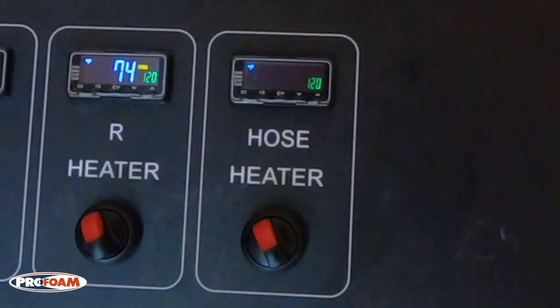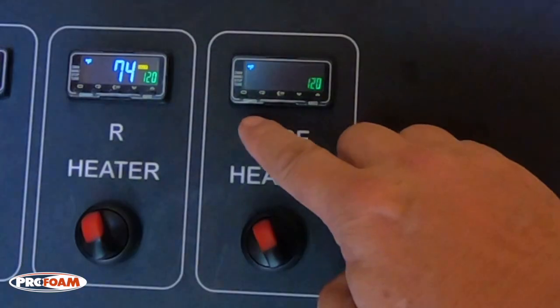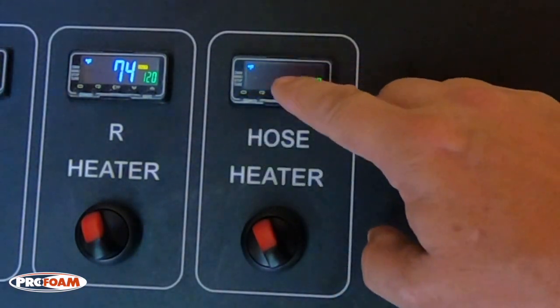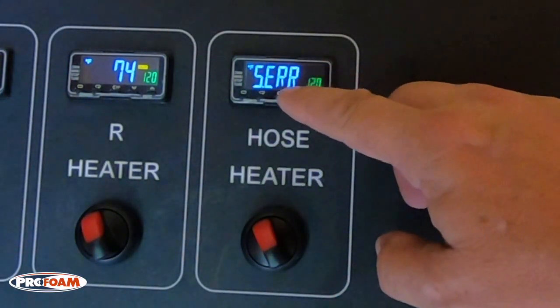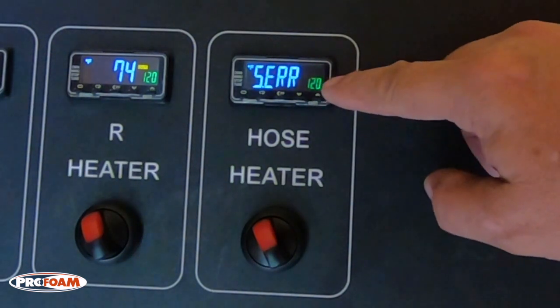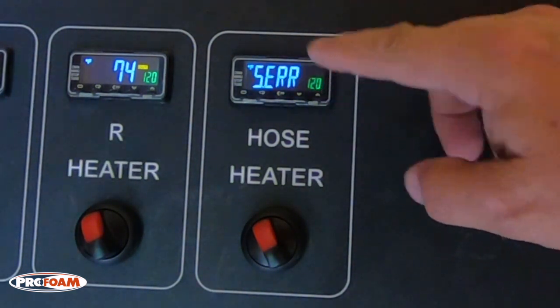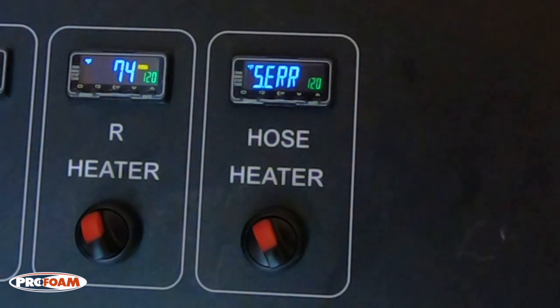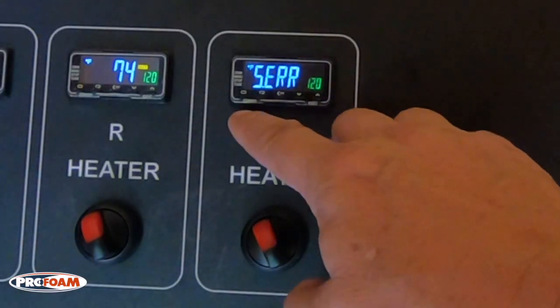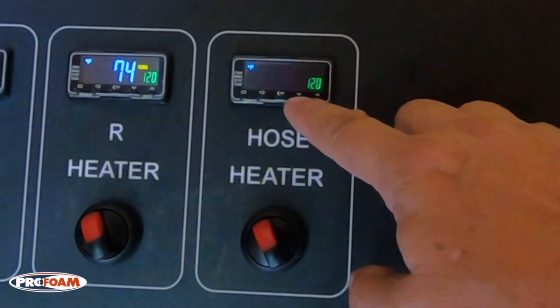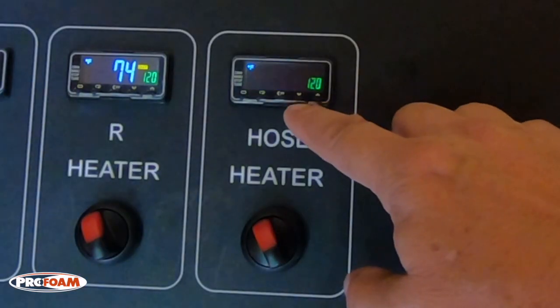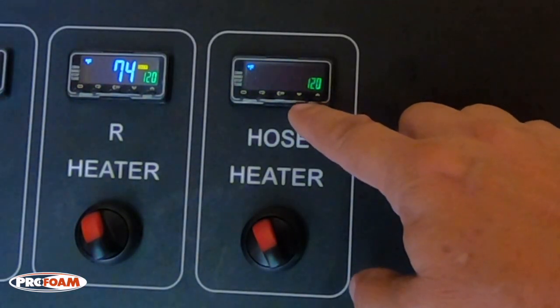So this is the Omron brand controller. You can see it says Omron right here. And we're getting an SERR error code for sensor error. And this is showing our set point. Although the controller can no longer read the sensor, so it doesn't know what to do. Along the bottom, there are 5 buttons. These 2 are for turning your temperature up or down when it's operating normally.